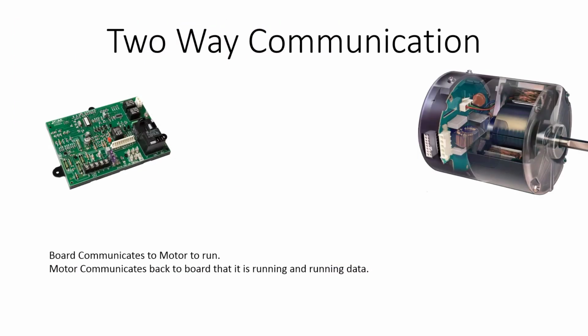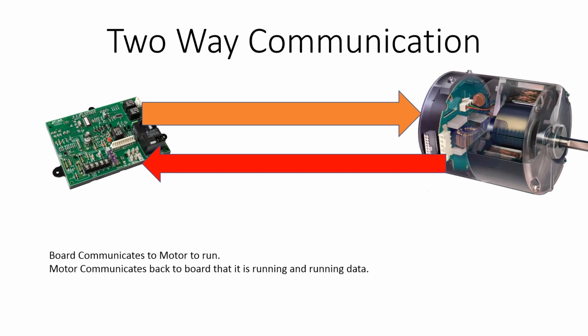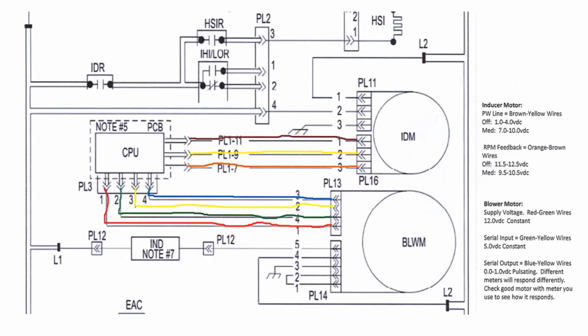Another type of communication between the board and the ECM motor is two-way communication. The board communicates to the motor that it wants it to run, and then the motor communicates back to the board that it's running and running data. Here we see a wiring schematic for the two-way communication.